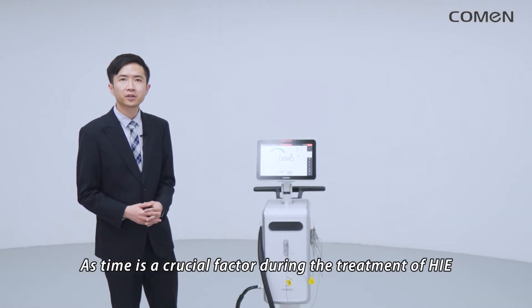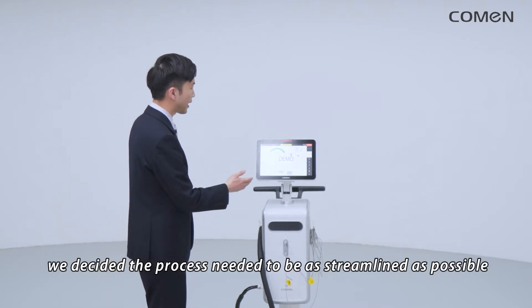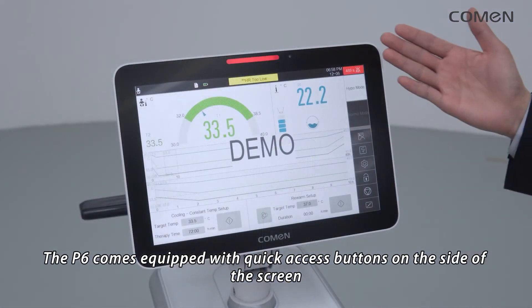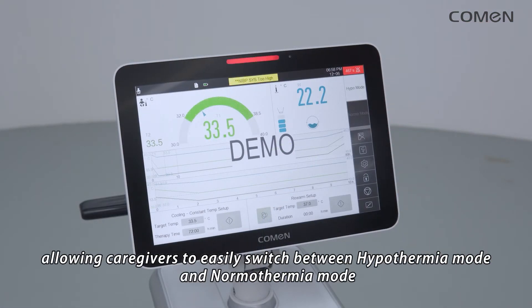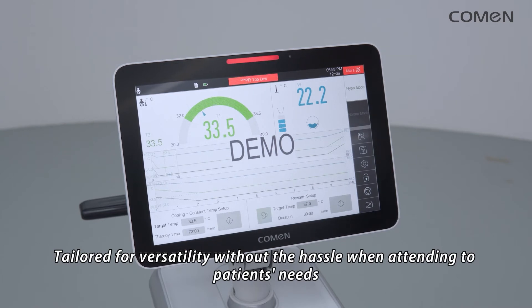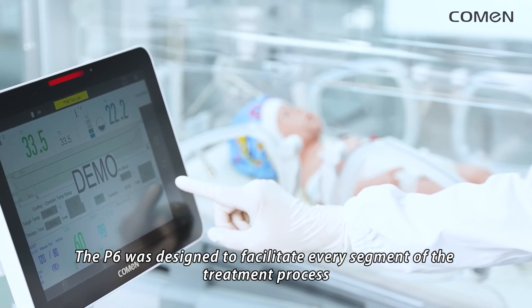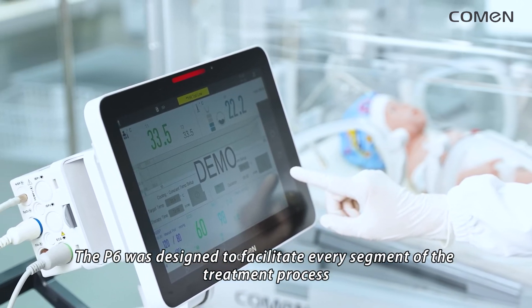As time is a crucial factor during the treatment of HIE, we decided the process should be as streamlined as possible. The P6 comes equipped with quick access buttons on the side of the screen, allowing caregivers to easily switch between hypothermia mode and normothermia mode, tailored for versatility without a hassle when attending to patients' needs.